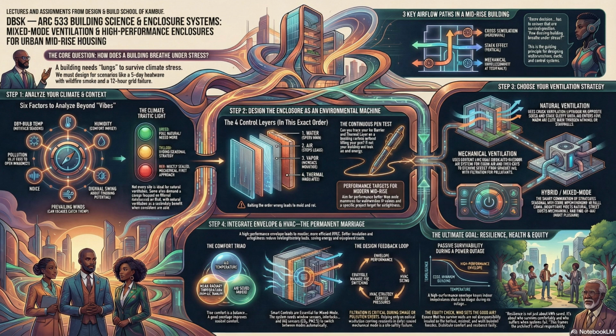We've established the machine and the breathing strategies. Now, Section 4, the marriage of systems: envelope HVAC integration. This is about that permanent, necessary feedback loop between the wall and the mechanical system. You cannot design these in isolation. The DBSK mandate is crystal clear on this. The wall is not just a thermal barrier. It is the first and most critical component of the HVAC system. Decisions you make on the envelope have monumental, lasting consequences for the HVAC infrastructure.